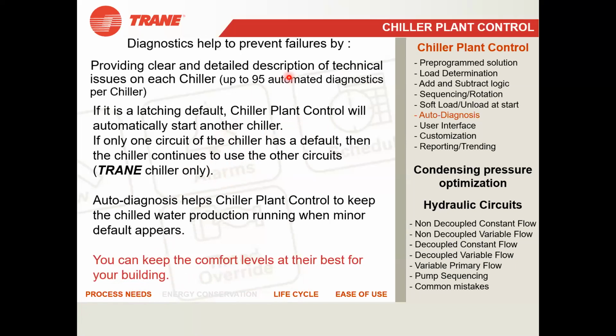Among these 95 automated diagnostics, I want to mention a few: discharge pressure, discharge temperature, oil temperature, internal refrigerant level, suction refrigerant temperature, discharge refrigerant temperature. These are just a few examples - there are many more, 95 parameters per chiller.